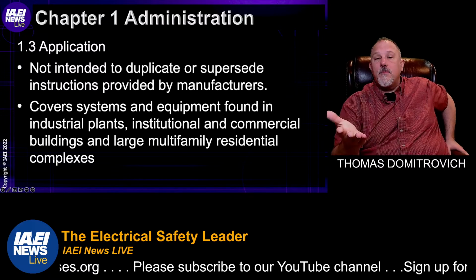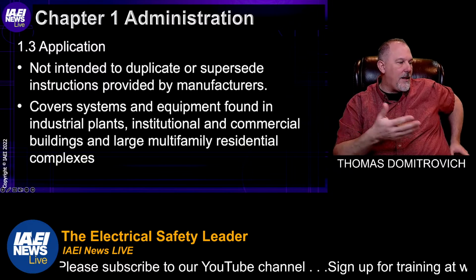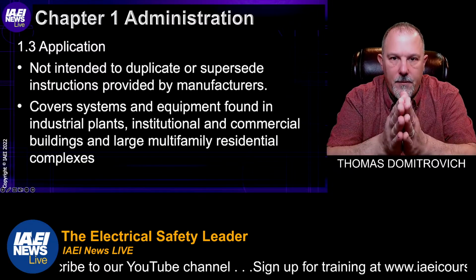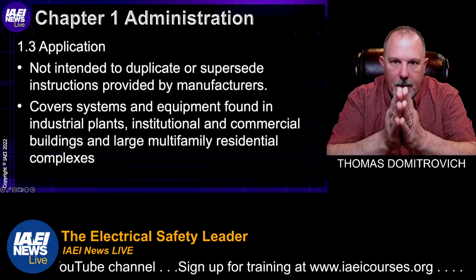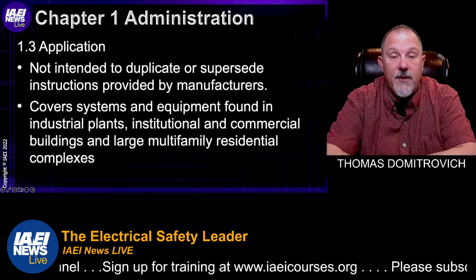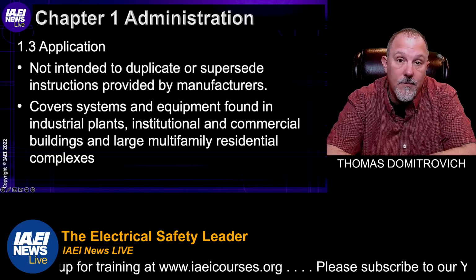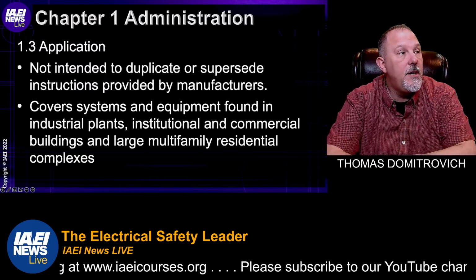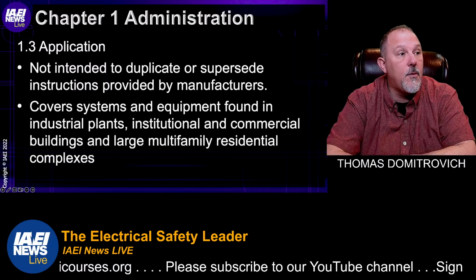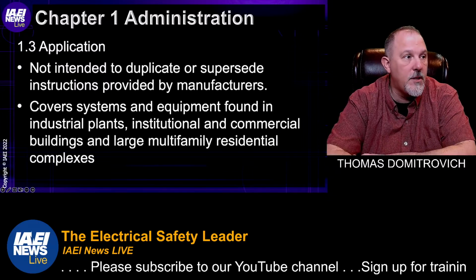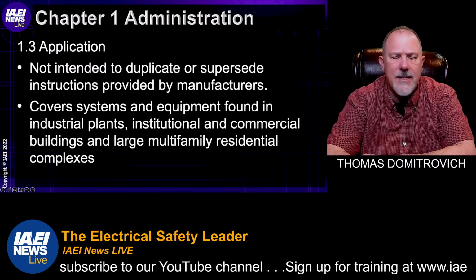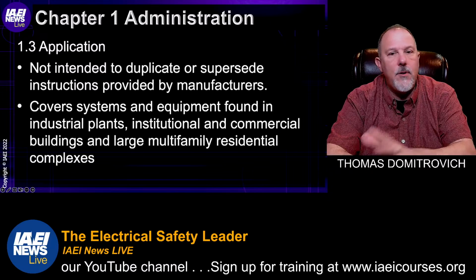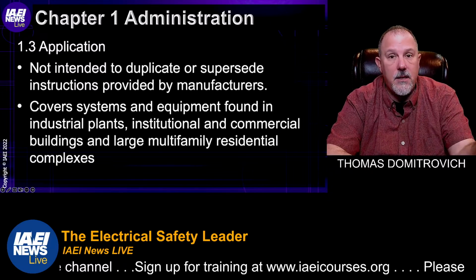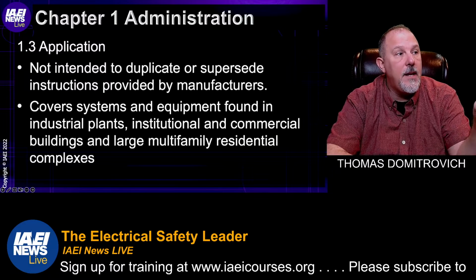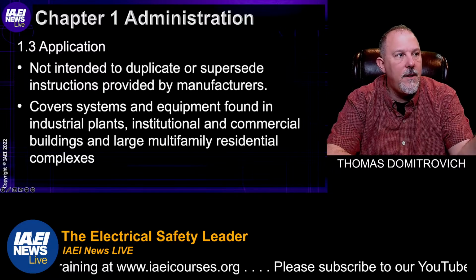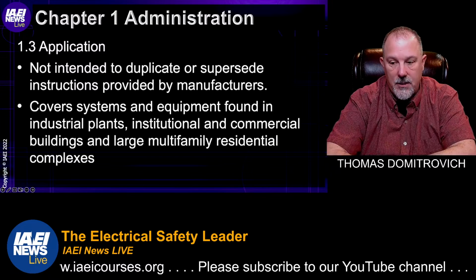And so here's my issue and my question. If I have a panel board - I'm going to call it the load center that you have in a residential dwelling unit - is that a panel board, right? This says systems and equipment covered are typical of those installed for industrial plants, institutional, commercial buildings, and large multifamily residential complexes. That doesn't mean it only applies to those areas. I would take that as meaning it applies to the systems and equipment that are typically found in those applications.